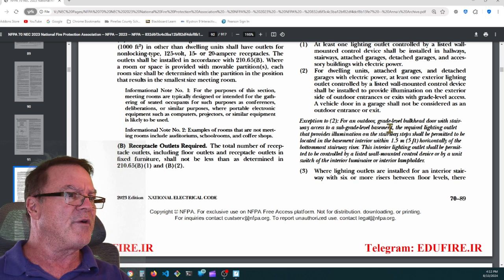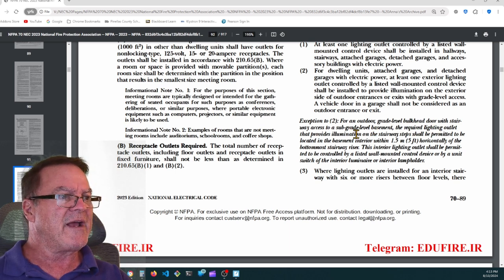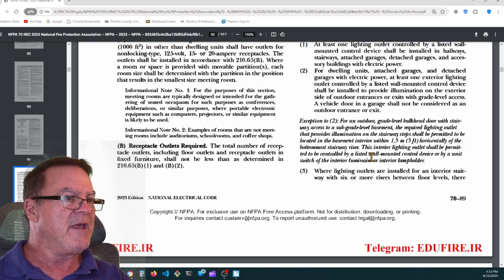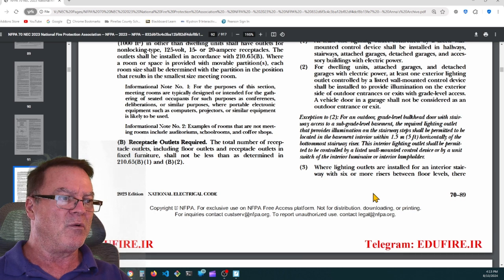Exception to number 2, for an outdoor grade level bulkhead door with stairway access to a sub-grade level basement. The required lighting outlet that provides illumination on the stairway steps shall be permitted to be located in the basement interior within 5 feet horizontally of the bottommost stair riser. This interior lighting outlet shall be permitted to be controlled by a listed wall-mounted control device or by a unit switch of the interior luminaire or interior lamp holder.